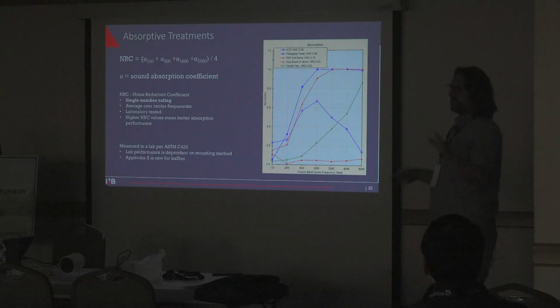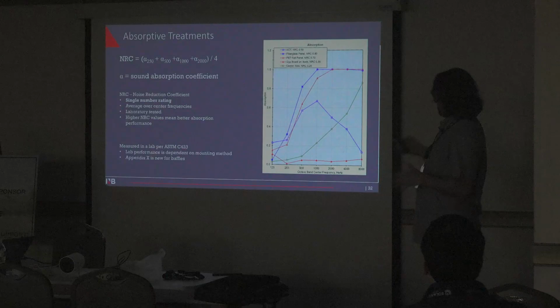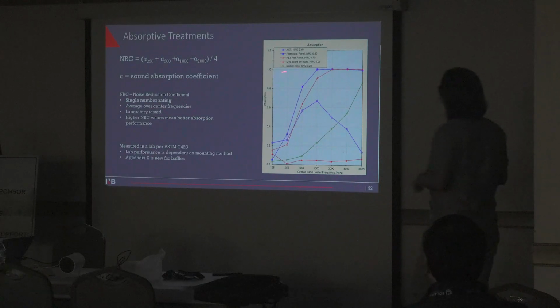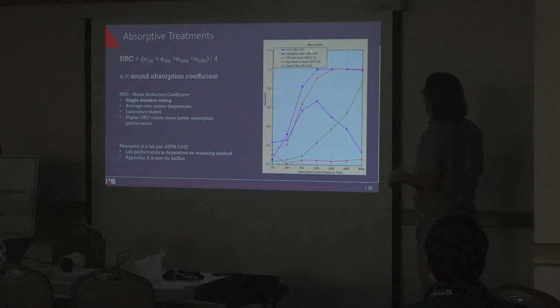For acoustics, we like to keep it around a 0.7 or so. Statistically, it's really one bounce and the majority of the noise is gone. But what you'll find is that this fiberglass panel says 0.8, so 80% of the acoustics is absorbed. That's pretty good. But when we get into the individual octave bands, we see that at 1000 hertz we get 1, and we are almost 100% at 1000 and above. We're close to 80 at 500, but when we get lower than that, we're really not doing much, right?